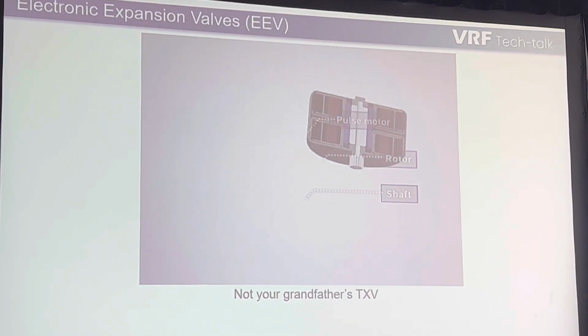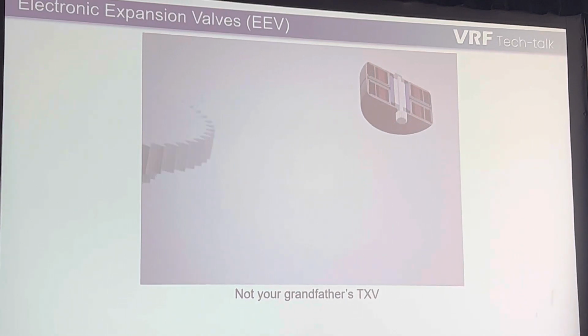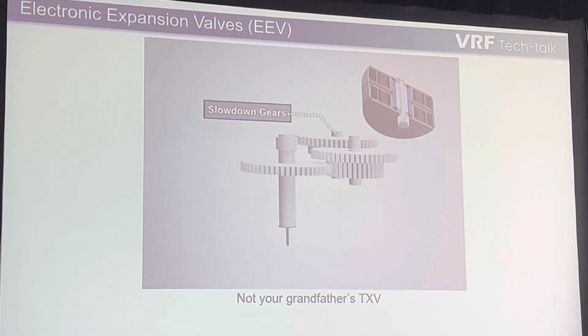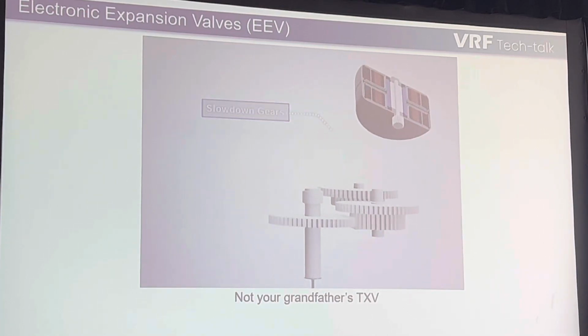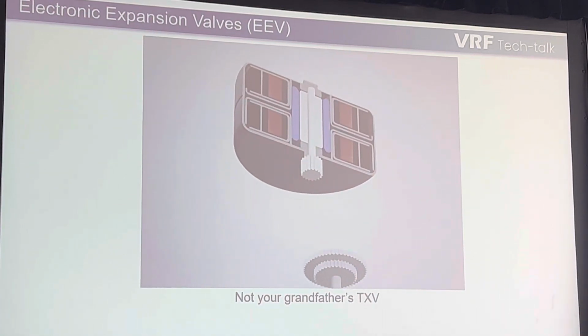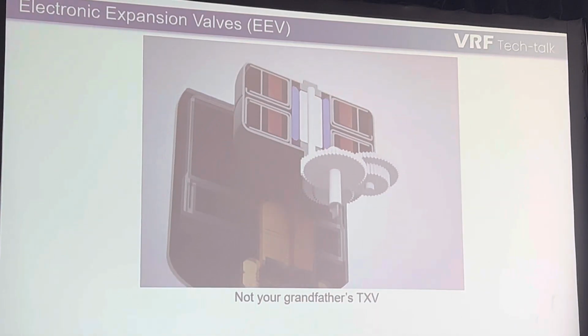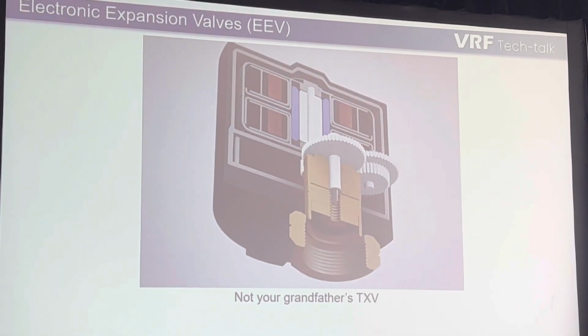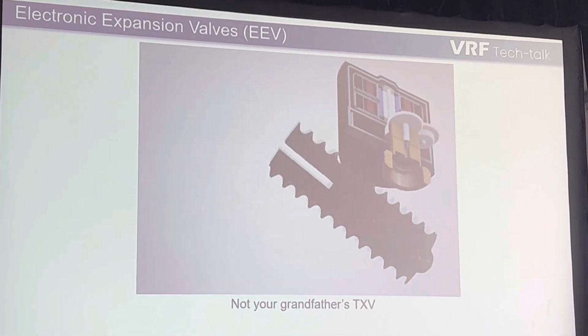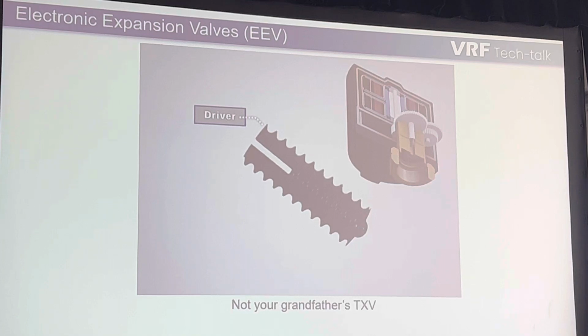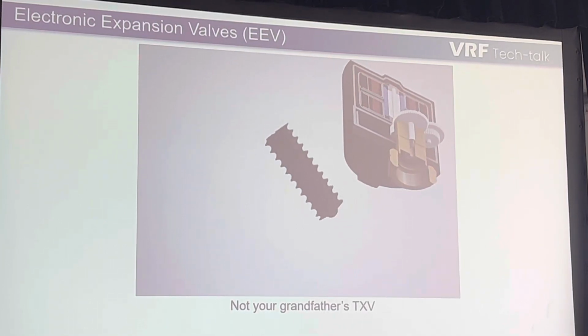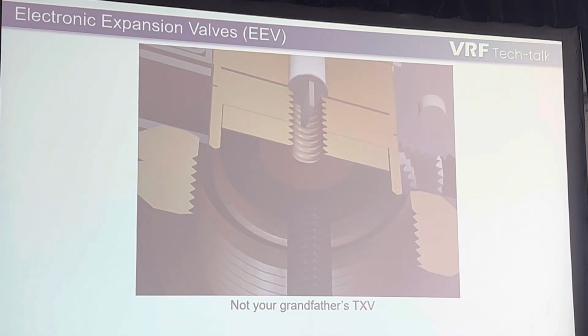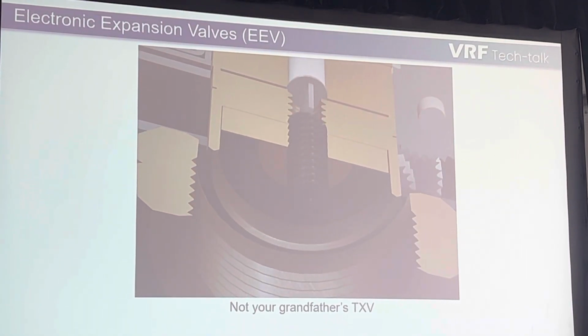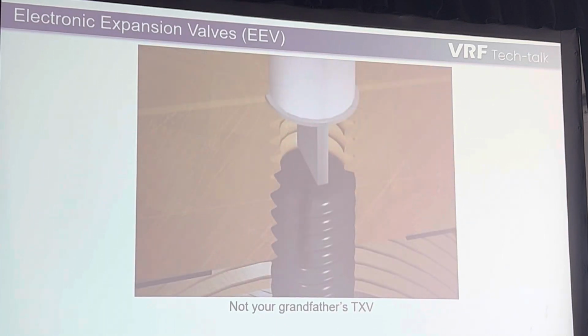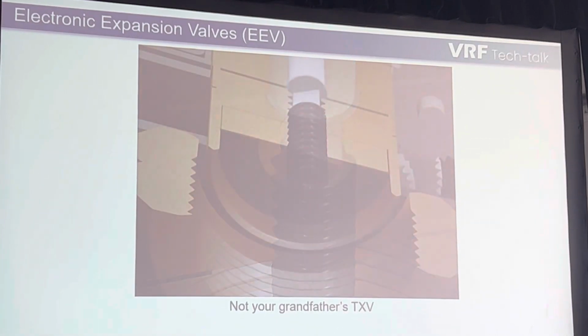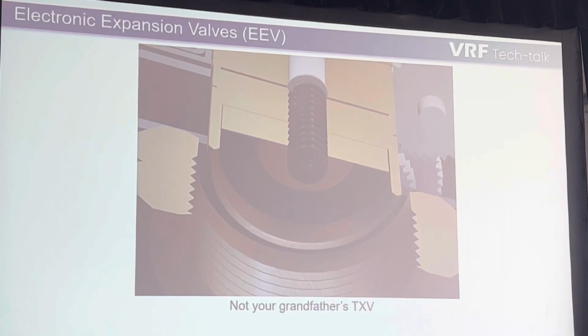You notice you have a pulse motor, you got the rotor, the shaft. We're going to go ahead and add some slow down gears to that. And as you can see, there's a center shaft there as well. In this electronic expansion valve, they're all housed in a waterproof enclosure. As you can see, that's a bolt-on. And then we have our driver. Typically, our driver is lubricated with some kind of silicone grease to prevent moisture intrusion into the valve. This is what's twisted and turned as it operates. These are to remain in contact with each other at all times.